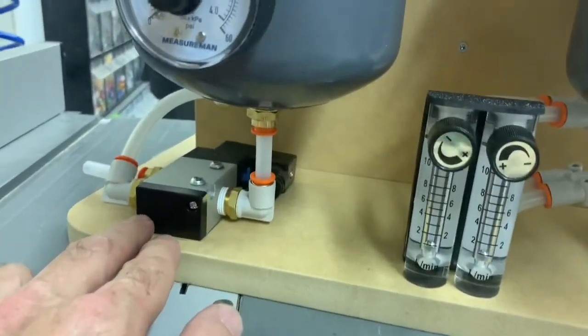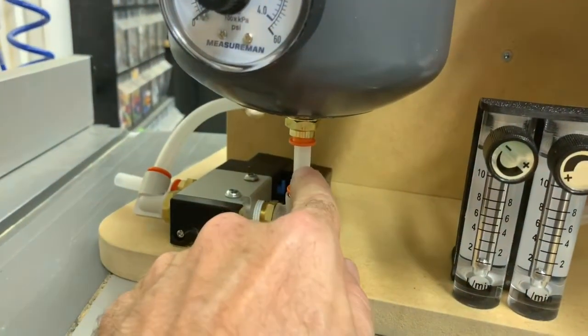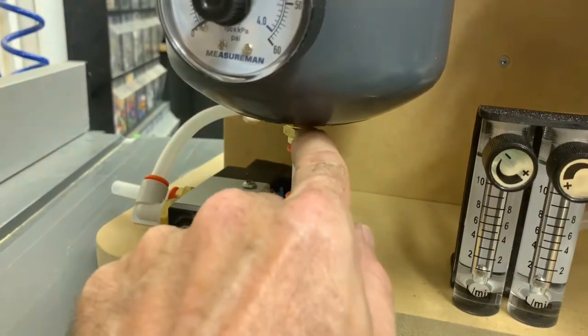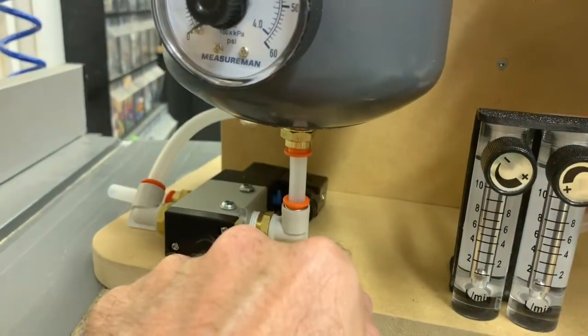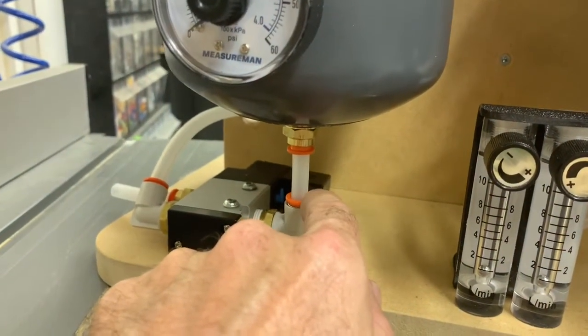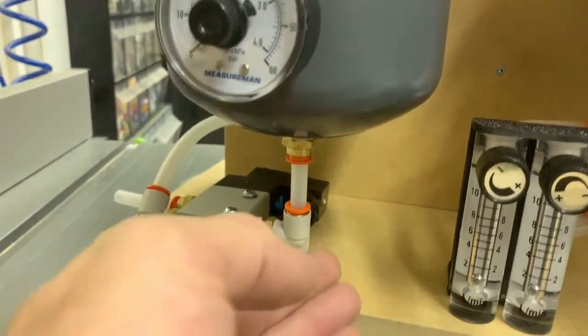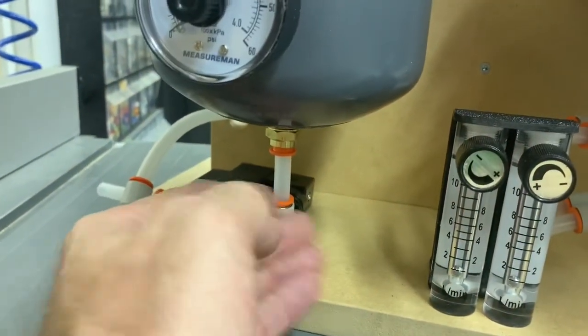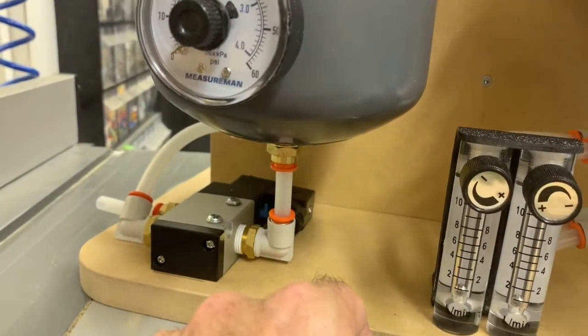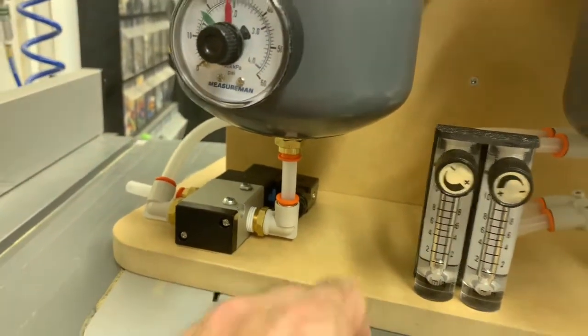Next refinement you'll notice is there's almost no tubing in between the valve and the sieve. We're working to minimize wasted air. Anything between the valves is wasted if it doesn't have zeolite in it. So we work to minimize that.